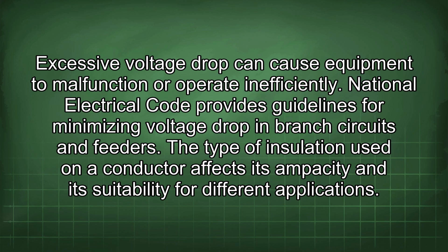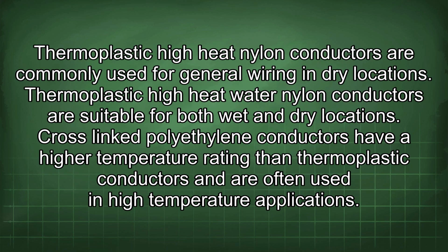The type of insulation used on a conductor affects its ampacity and its suitability for different applications. Thermoplastic high-heat nylon conductors are commonly used for general wiring in dry locations. Thermoplastic high-heat water nylon conductors are suitable for both wet and dry locations. Cross-linked polyethylene conductors have a higher temperature rating than thermoplastic conductors and are often used in high-temperature applications.